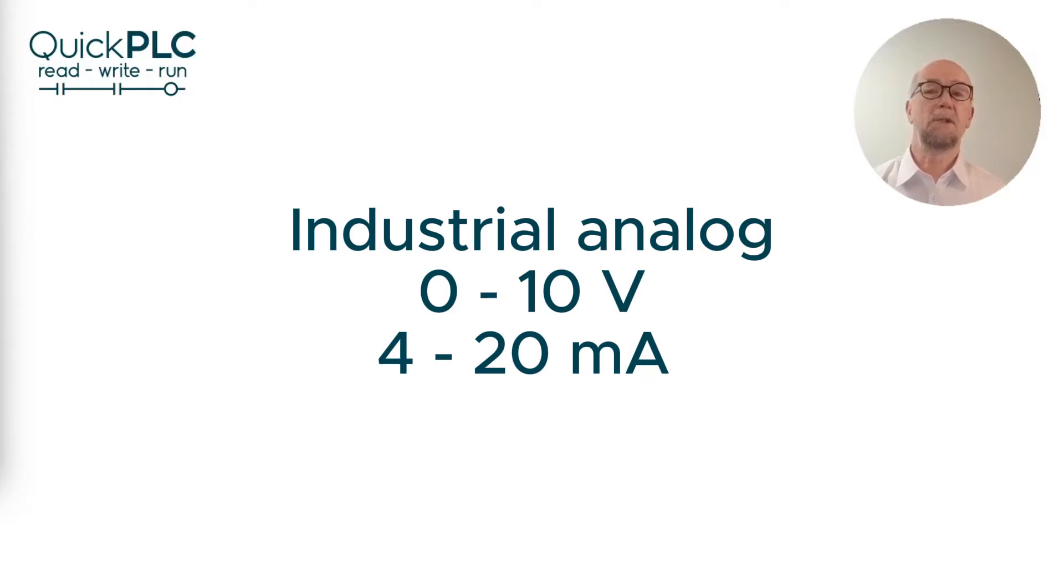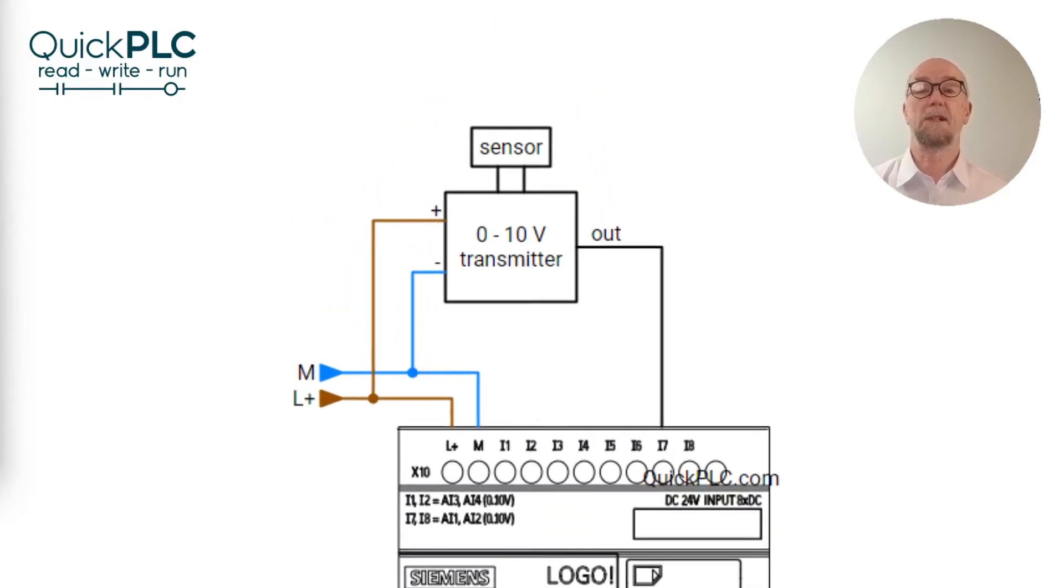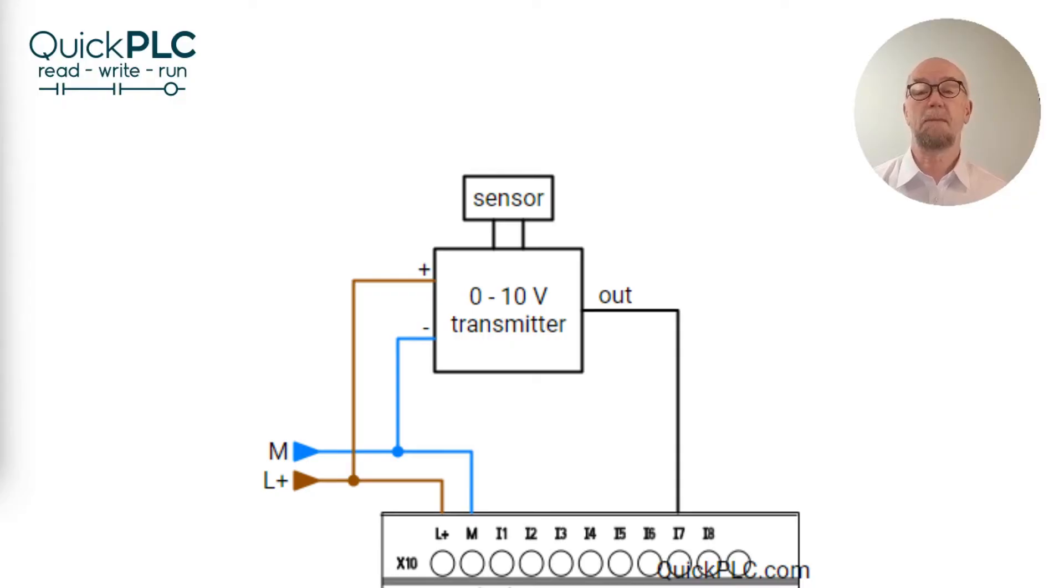The two most common standards for analog signals in industrial control are 0 to 10 volt and 4 to 20 milliamp. 0 to 10 volt sensors are wired up as shown. They're simple but have several disadvantages. They need three wires. The 0 to 10 volt signals are susceptible to electrical noise due to the high input resistance of the Logo's analog inputs and you can't tell the difference between a zero measurement and a disconnected sensor.